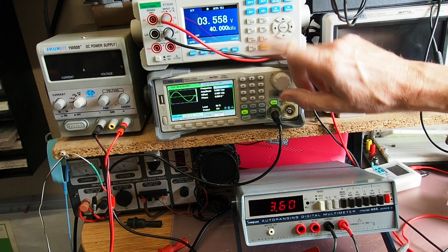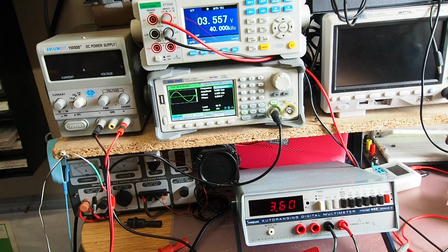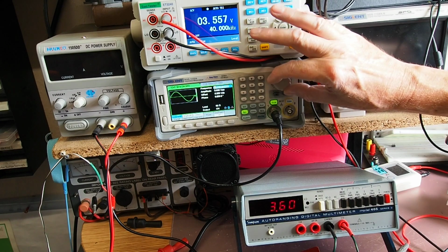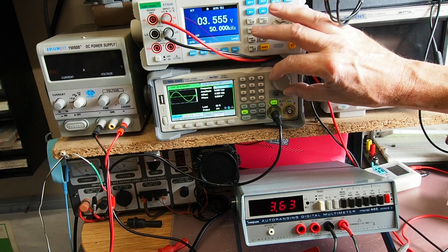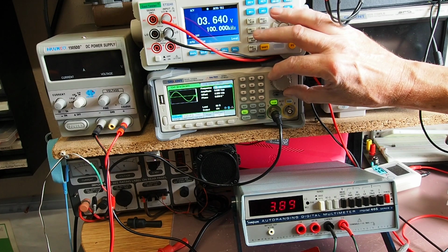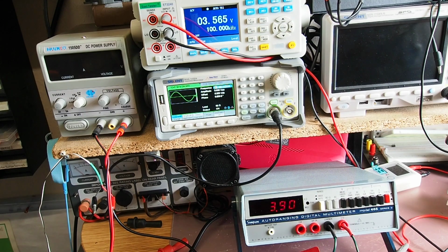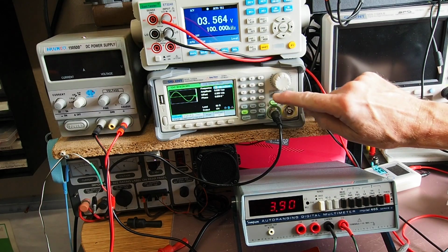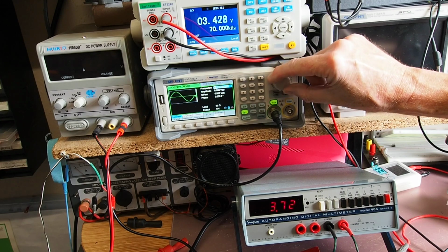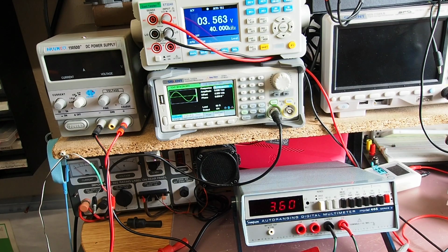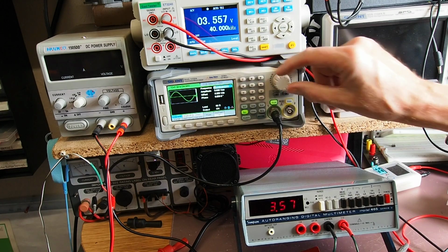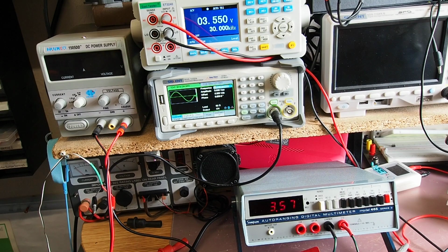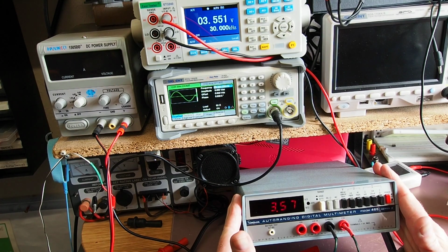Starting to creep up a little bit now, so starting to lose accuracy, but that's 40 kilohertz, so that's pretty good. And if I go absolutely stupid and go up to 100 kilohertz there, yeah, okay, it's a little bit off now, but certainly if I hop back down to about 40 kilohertz, still 30 kilohertz there, I'm getting quite a sensible reading, so very pleased.